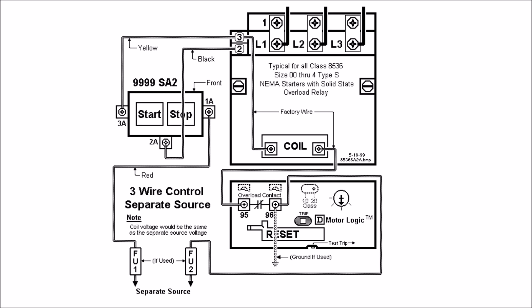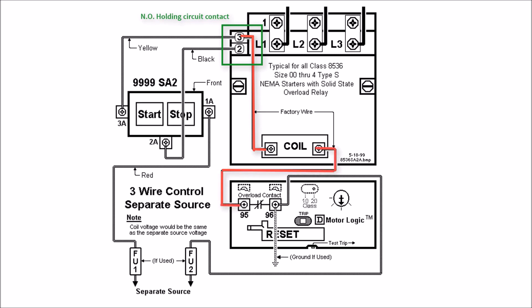From the factory you're actually going to get a wire from 95 to this right-hand side of your coil as well as terminal 3 down to the left-hand side of your coil. This contact up here is actually going to be used as your holding circuit in the three wire control that we'll go over.